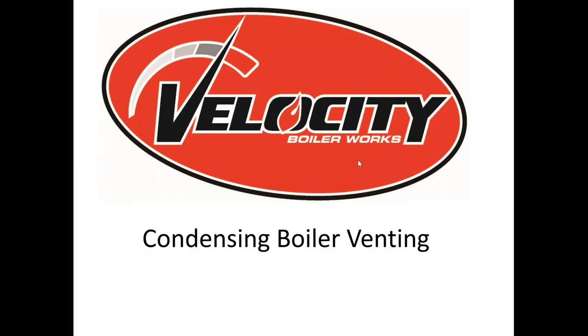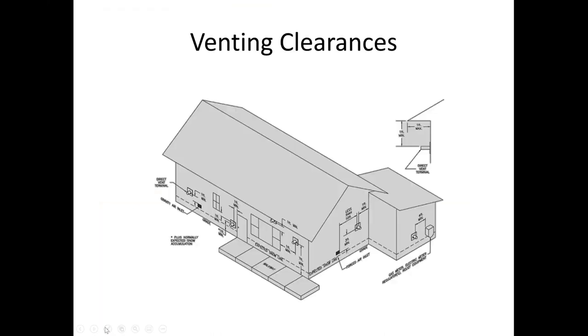So our entire condensing line is going to vent primarily the same. In the front of the I&O manual, there's going to be this wonderful little drawing of the house. And our products are not going to vent that much differently than most direct vent appliances. We need to be 1 foot away from any operating door or window. We need to be 12 inches, not 12 feet. We're 12 feet above it, might as well be on the roof. Sorry about that. 12 inches above our nominal snow line, whatever that may be, varies from area to area. City of Philadelphia, we really haven't had snow in quite some time.